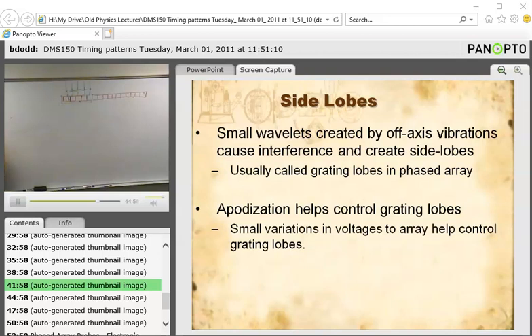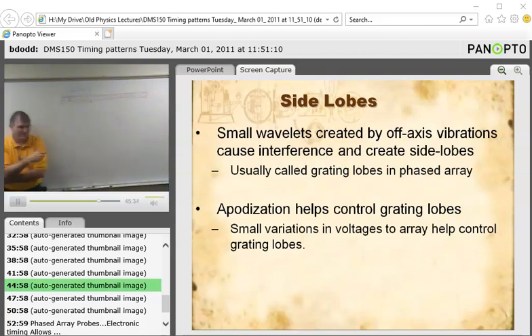Yep. And that's all at the same time as the steering and the timing. So this is all going on at the same time as the electronic steering and the electronic focusing. So what it comes down to, though, is apodization is small variables in voltage to reduce grating lobes. And you're not going to be asked to go in there and figure out what the apodization changes should be for any given transducer. We're going to let the guys that built it do that. But we do have to know what apodization is, just as another word for our vocabulary.